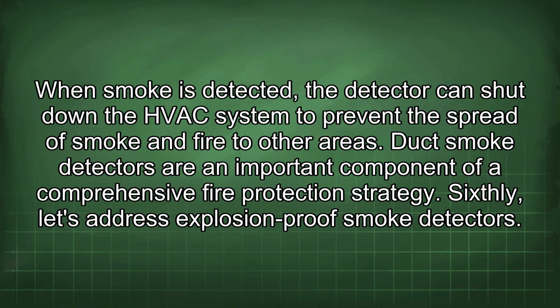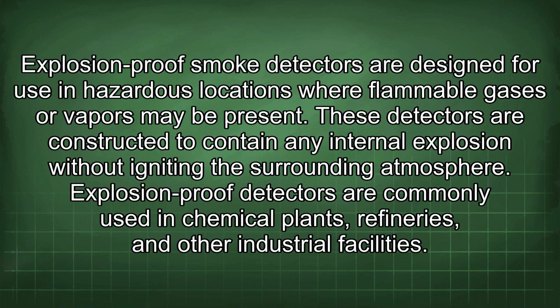Sixthly, let's address explosion-proof smoke detectors. Explosion-proof smoke detectors are designed for use in hazardous locations where flammable gases or vapors may be present. These detectors are constructed to contain any internal explosion without igniting the surrounding atmosphere. Explosion-proof detectors are commonly used in chemical plants, refineries, and other industrial facilities.